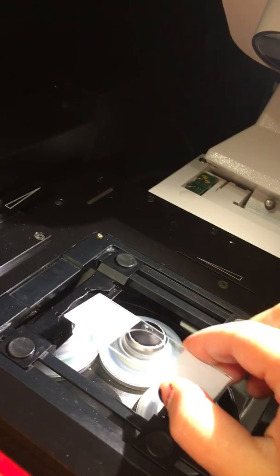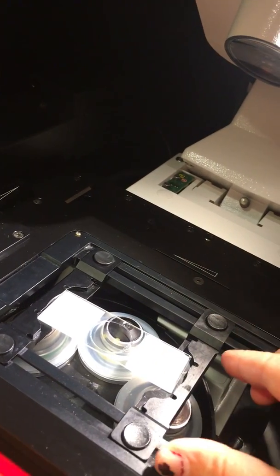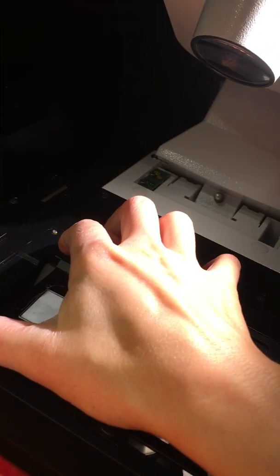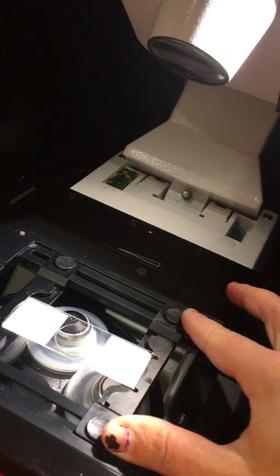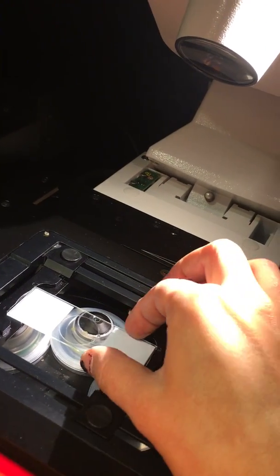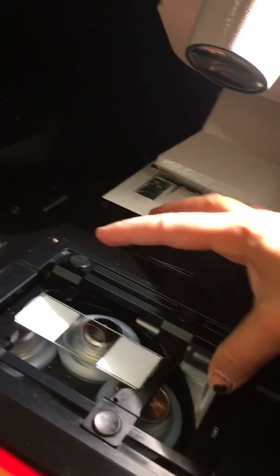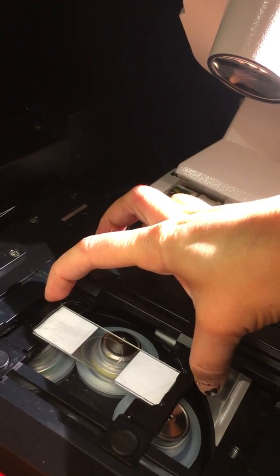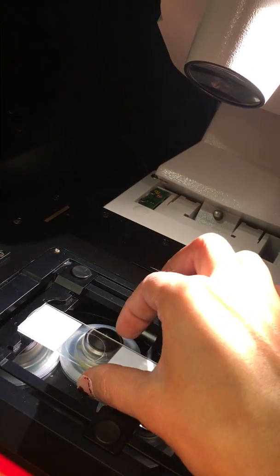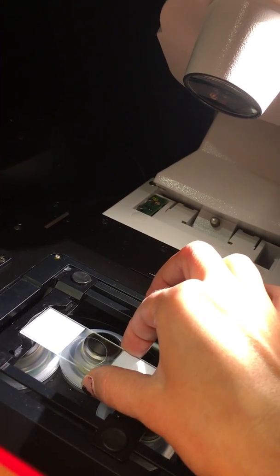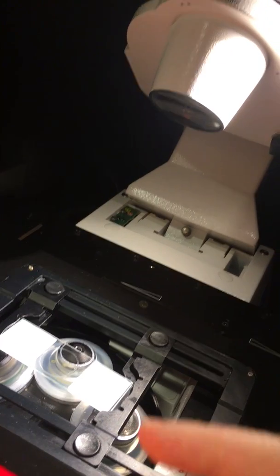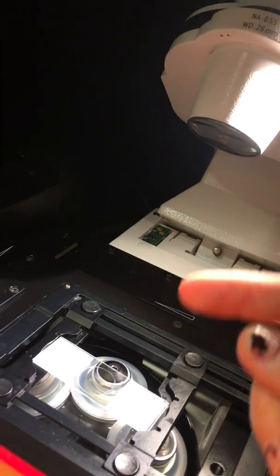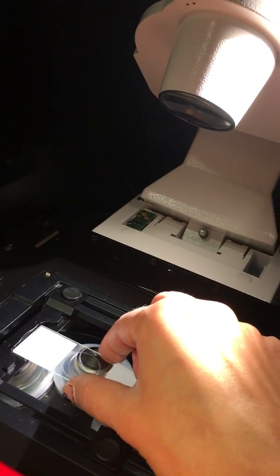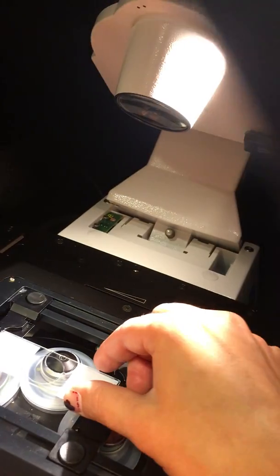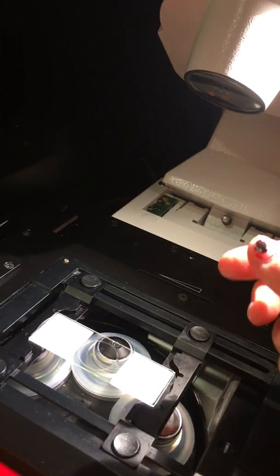Then place your sample between these two sliding holders, and you can adjust the holders' position as you wish. I would advise you not to press these holders too tight, for the sample to be able to be lifted up. In case you use a high magnification lens and accidentally run it way too high, it will just lift your sample instead of cracking it. And we don't want to crack your sample, in order not to scratch the glass of the lens.